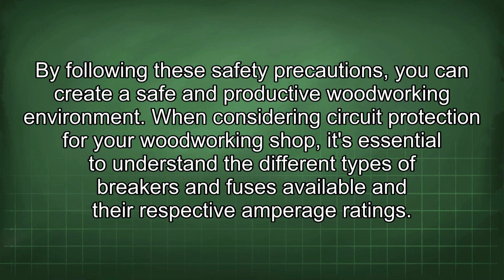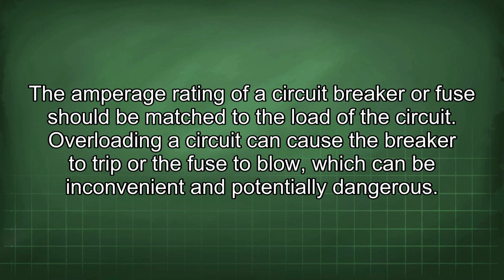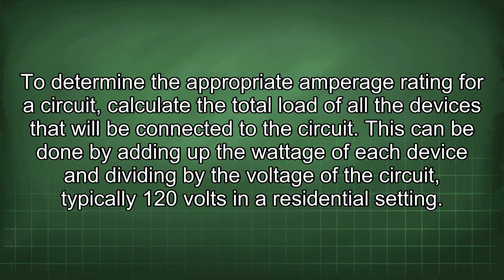When considering circuit protection for your woodworking shop, it's essential to understand the different types of breakers and fuses available and their respective amperage ratings. The amperage rating of a circuit breaker or fuse should be matched to the load of the circuit. Overloading a circuit can cause the breaker to trip or the fuse to blow, which can be inconvenient and potentially dangerous. To determine the appropriate amperage rating for a circuit, calculate the total load of all the devices that will be connected to the circuit.